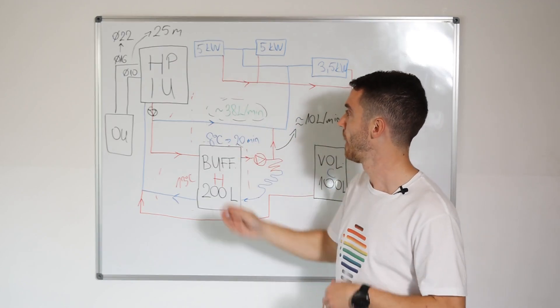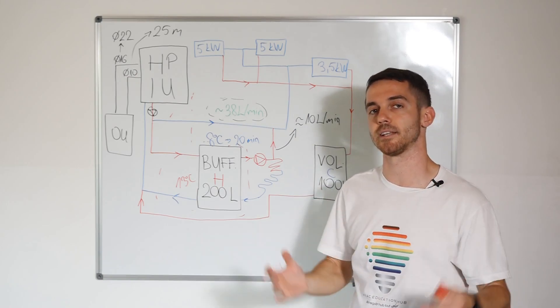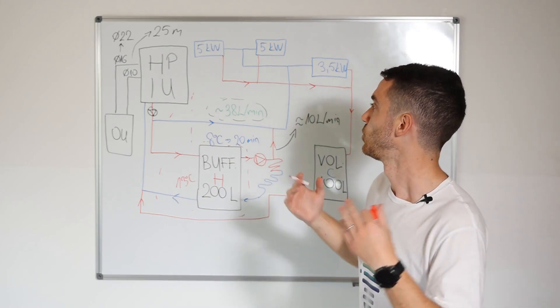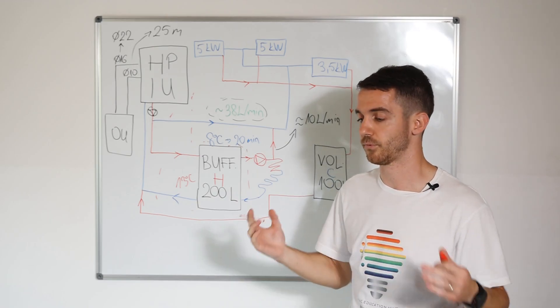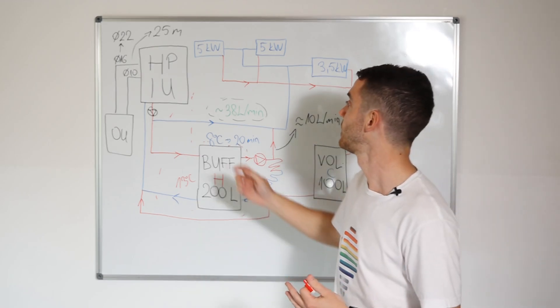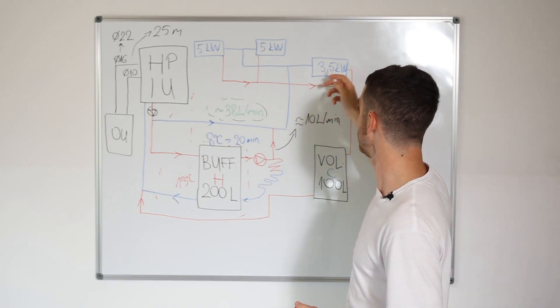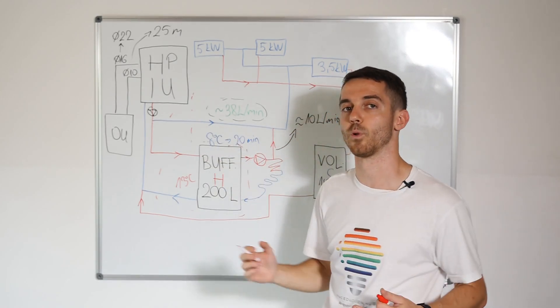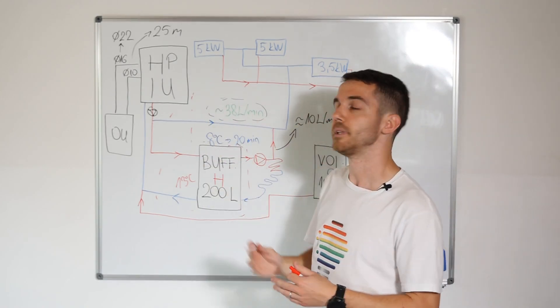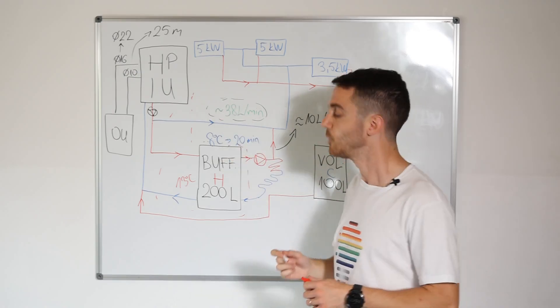So heat pump, early heat pump has sensors, algorithm to stop the unit if set point is reached or if it's too cold. But for very low flow rate, so for this only 3.5 kilowatt, very low flow rate, it cannot stop immediately. And in that case, you have the problem.